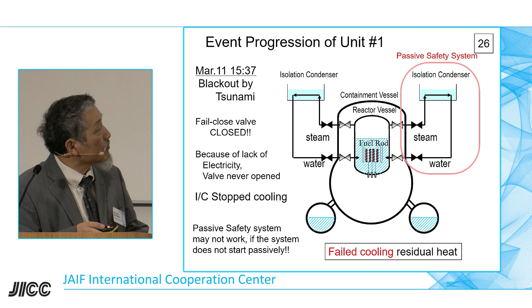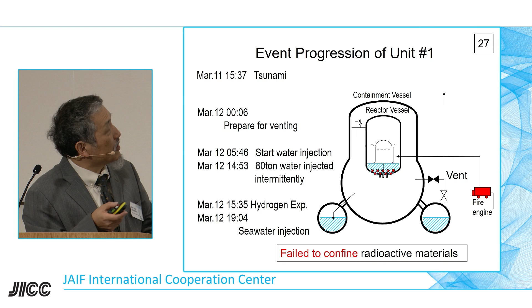And because this system doesn't work, the reactor core may dry out, and then core melt happens. So this fails the residual heat cooling system. Okay, it doesn't work. After that, they tried to supply water from the fire engine, and it was then in a normal operation condition, but it may fall down, and unfortunately, a hydrogen explosion also happens.